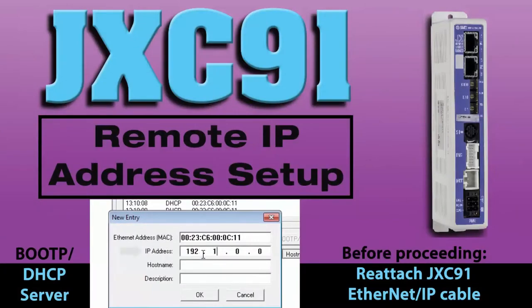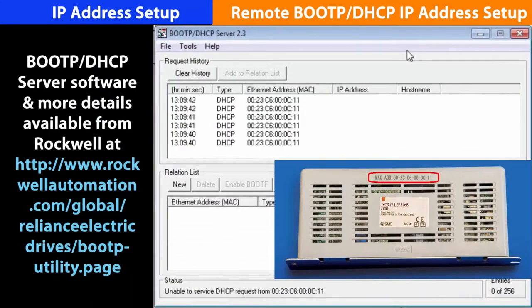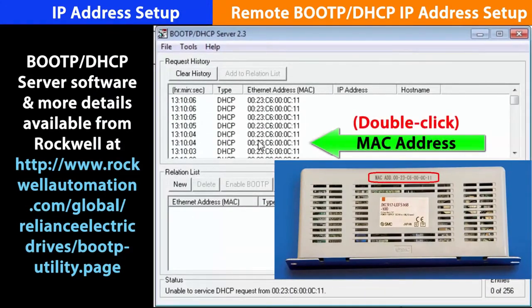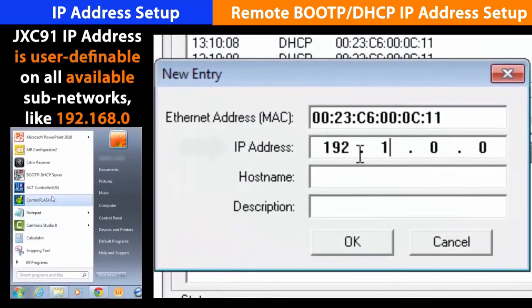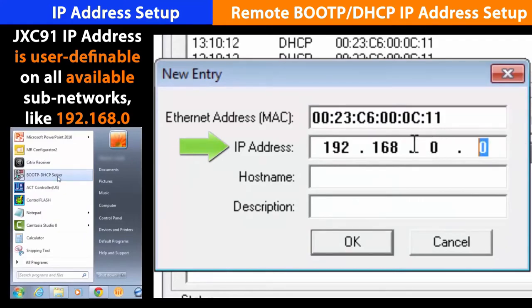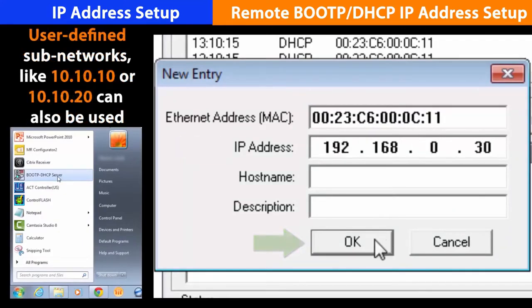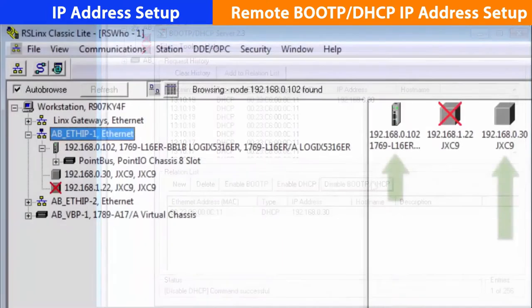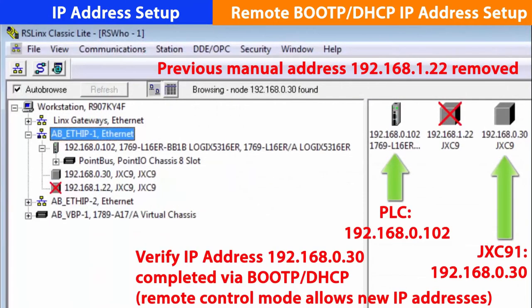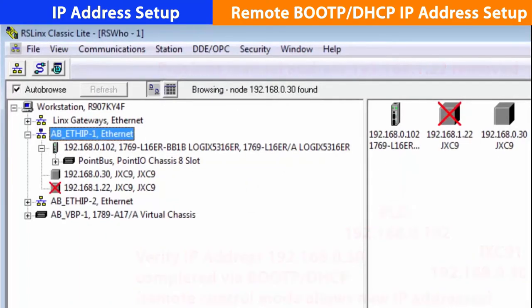Now we can set the IP address from the PC. Start the BootP DHCP software. Once BootP is running, apply power to the JXC-91. Double click on the MAC address and enter the IP address into the box. We'll choose 192.168.0.30. Hit OK. Highlight the IP address and click disable BootP DHCP. You should see command successful. To verify that all IP addresses are set, start RSLinx and it will ping the JXC-91 and other nodes to make sure everything is communicating.